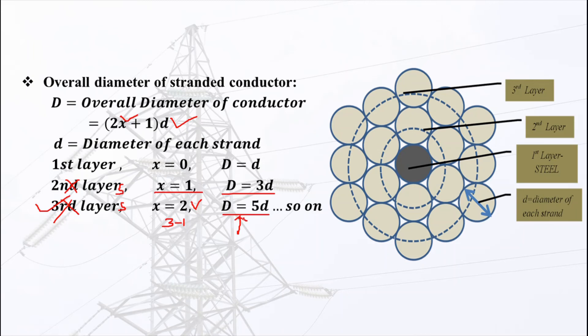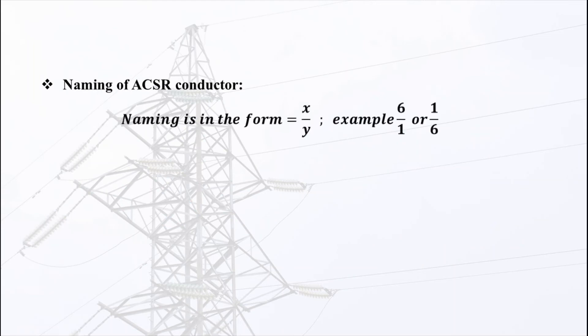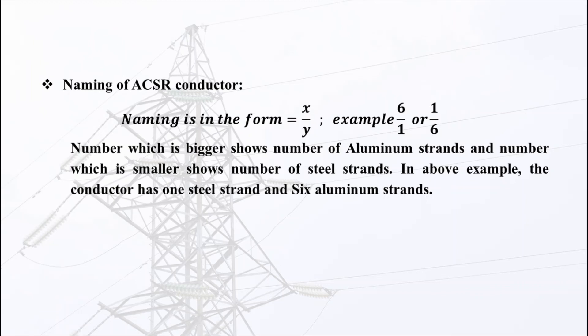Now we will discuss the nomenclature of a composite stranded conductor. The naming is given as a fraction x/y, for example 6/1 or 1/6. The larger number denotes the number of aluminum strands, and the smaller number denotes the number of steel strands. So in 6/1, there are 6 aluminum conductors that carry current and 1 steel conductor for tensile strength.